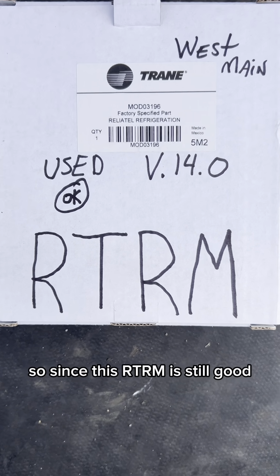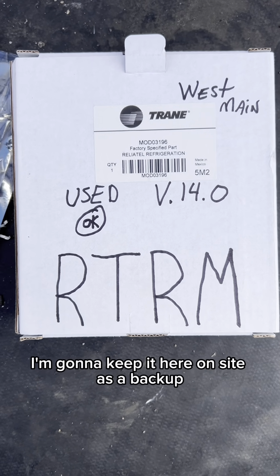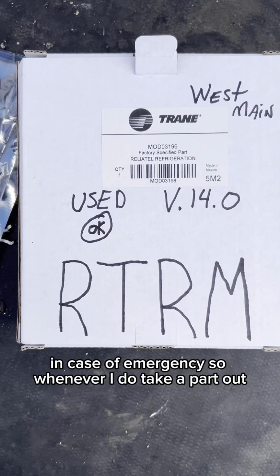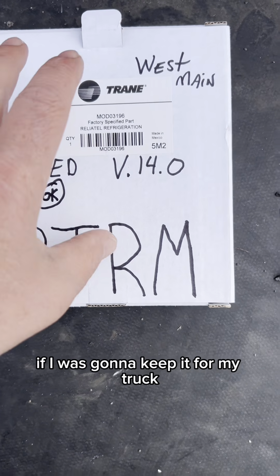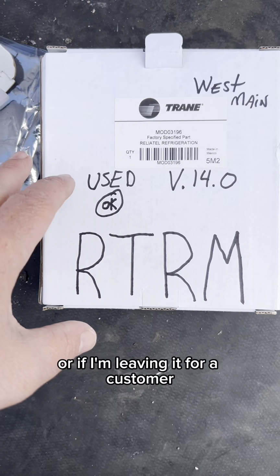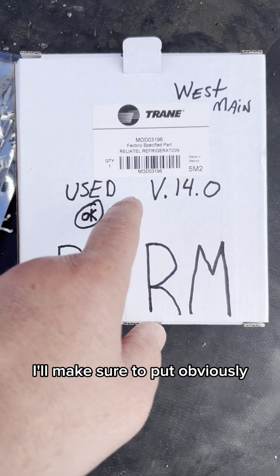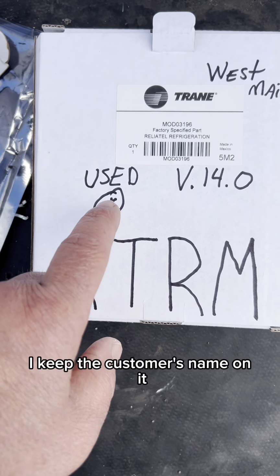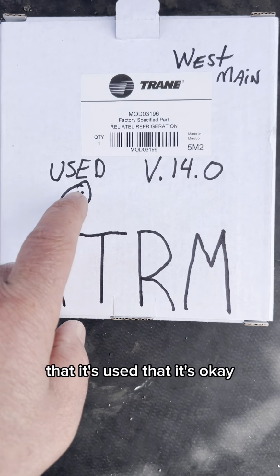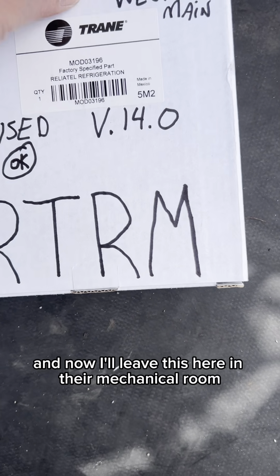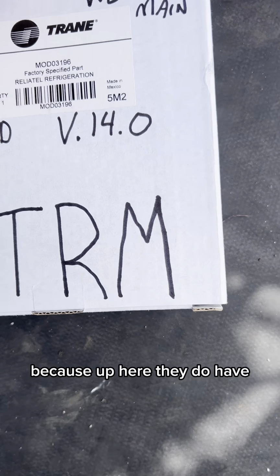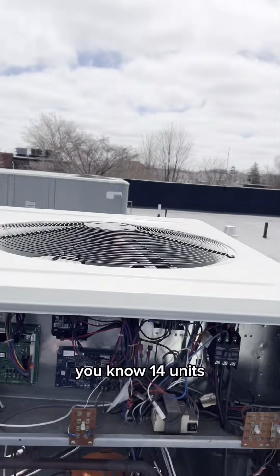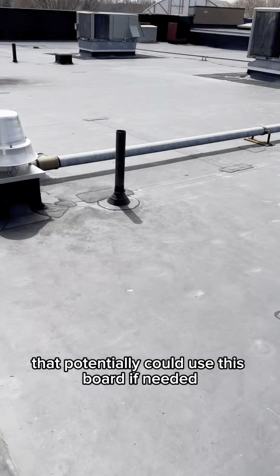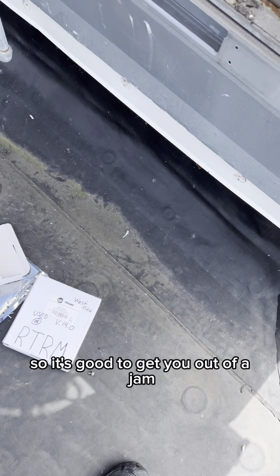Since this RTRM is still good, I'm going to keep it here on site as a backup in case of emergency. Whenever I take a part out, whether I'm keeping it for my truck or leaving it for a customer, I'll keep the customer's name on it, note that it's used, that it's okay, and what version it is. And now I'll leave this here in their mechanical room because they have 14 units that could potentially use this board if needed. So it's good to get you out of a jam.